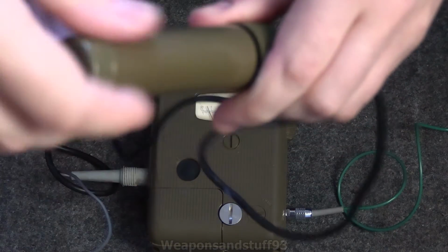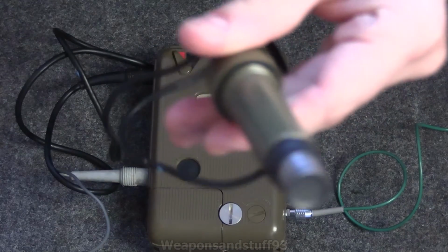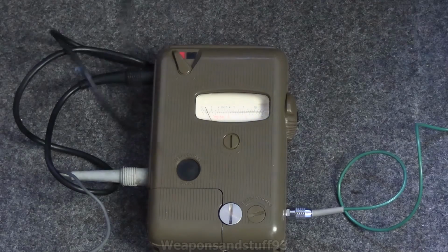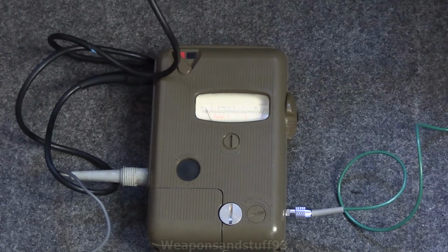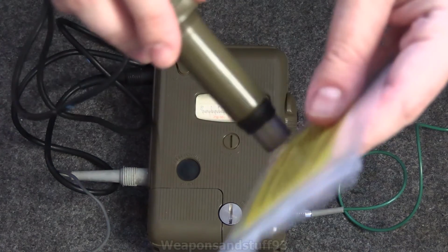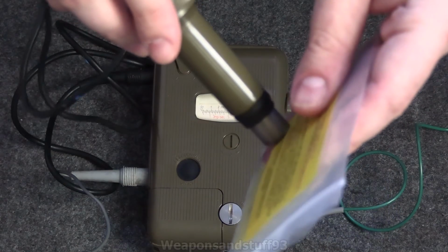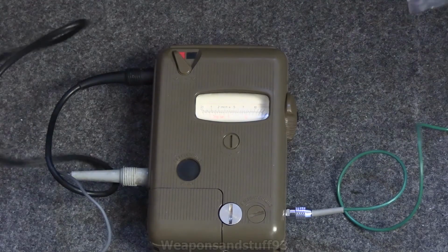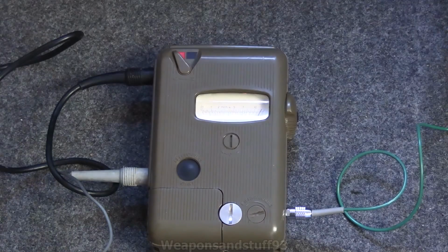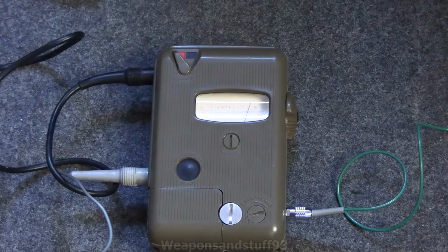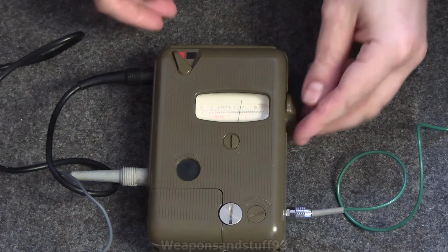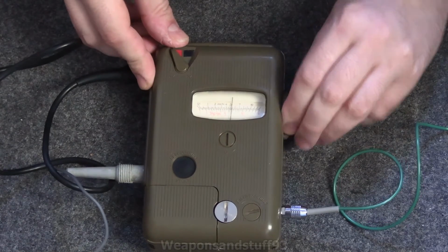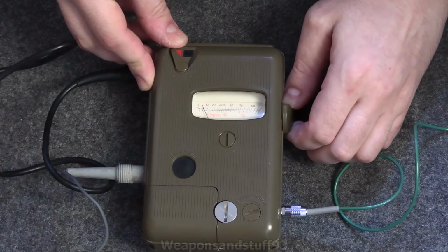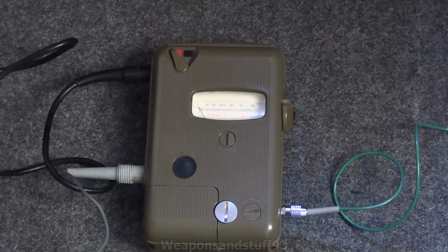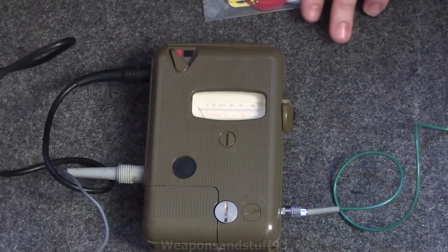You can also, if you really wanted to, and I wouldn't recommend it because of contamination reasons, take the probe apart like that, and then you can directly put a sample close to the little window. So with that open like that, I'm going to test in case this does pick up alpha radiation in a minute, but let's first just see how high this will go on the scale. So if we put that to the 1 to, is that 100 milliroentgen scale, I think now?